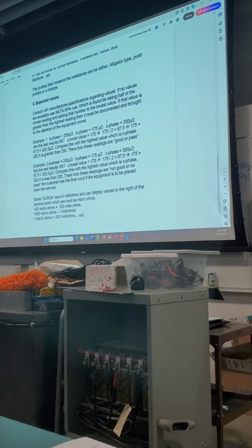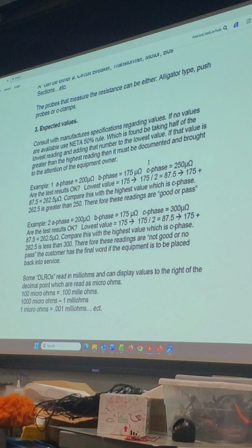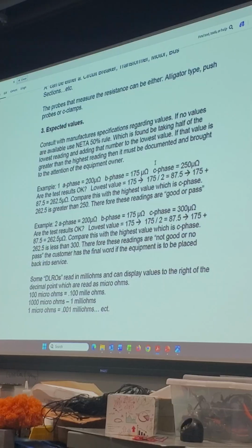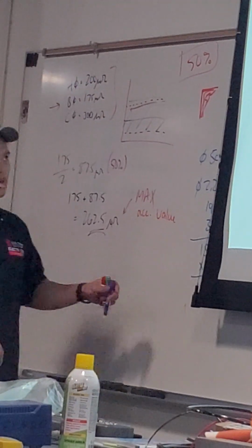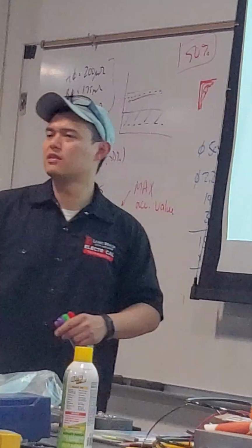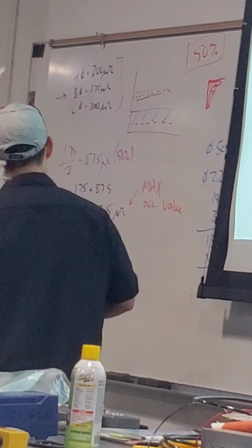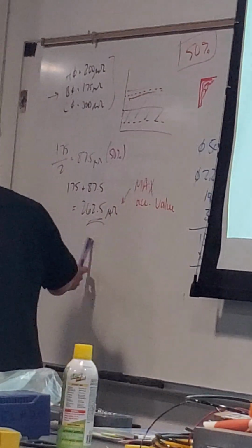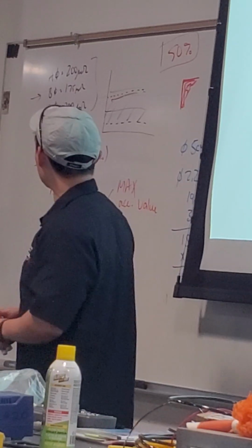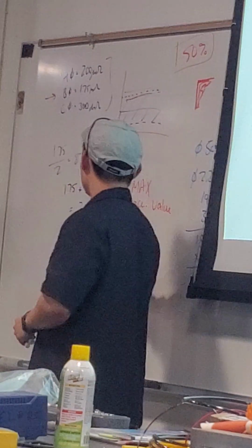So example 2: A phase, 200 microohms. 175 still good. Oh no, what's going on with C phase? Maybe you tested this a year later, two years later, five years later — maybe they only paid for five-year PM cycles. This one went up to 300. Which of these is the lowest value? Still the lowest value, just safer in the writing. So that means our acceptable maximum value is still 262.5.